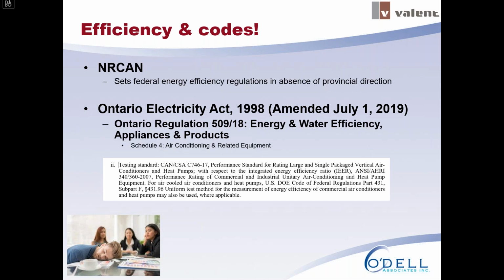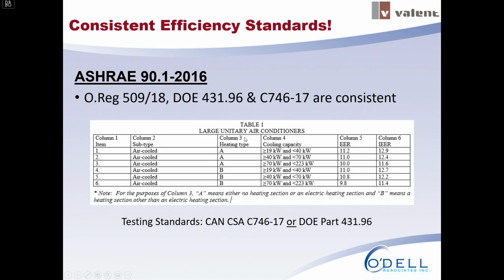So if I move on and talk a little bit more about these efficiency standards, it's quite interesting that if you look through Ontario Regulation 509-18, and then you look at DOE Standard 431.96 and C746-17, they are all consistent with each other in that they reference ASHRAE Standard 90.1 2016 efficiency requirements. Now, this table I'm showing here is not the full table. I've just pulled out the cooling capacities that I'm focusing on in this presentation. That table is much larger and has a lot more information on it, but I've pulled out what's important to today.